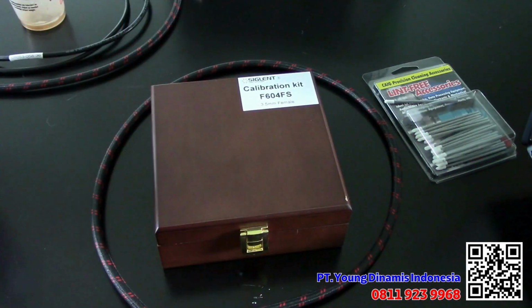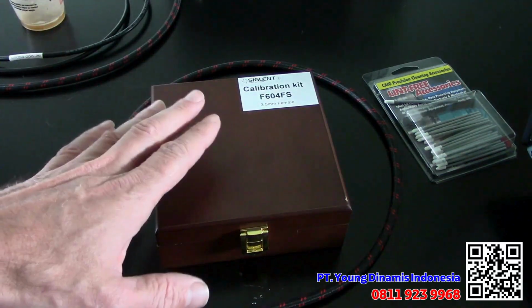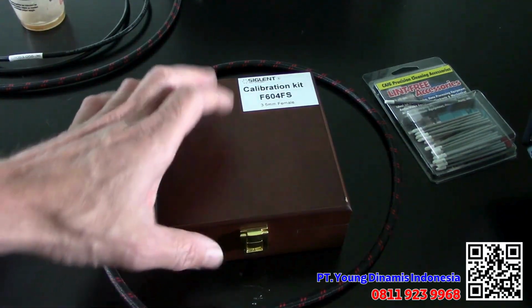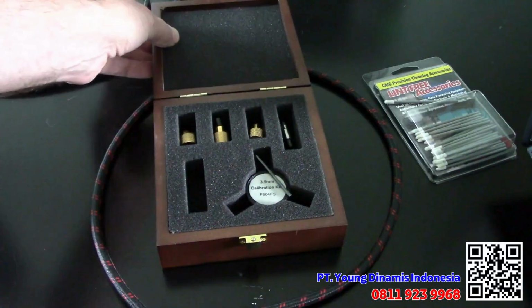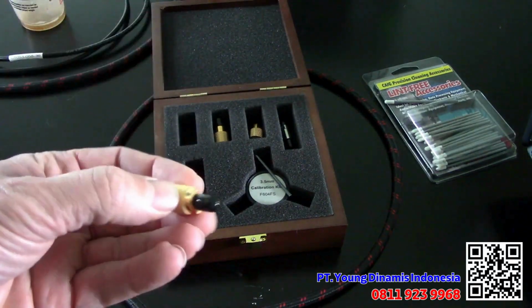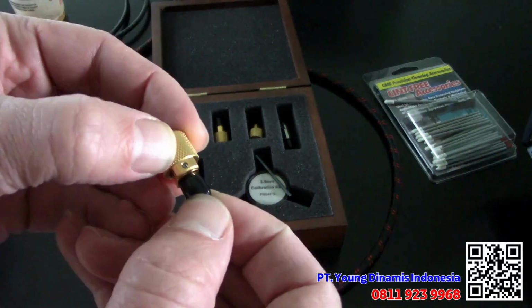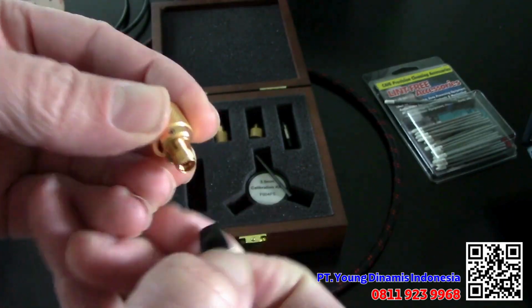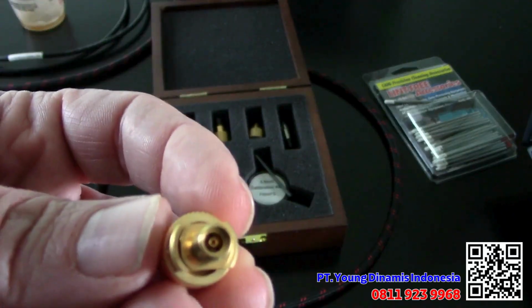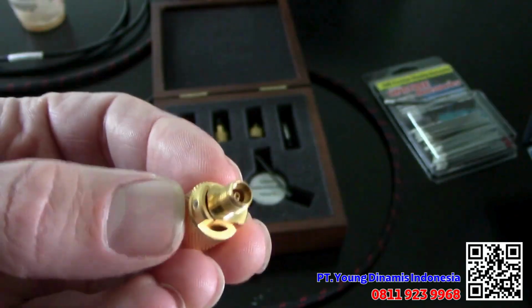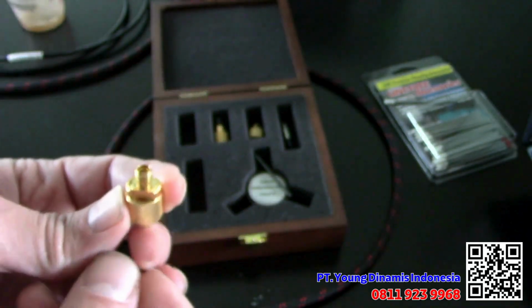Here we've got a Siglent F604FS female calibration kit. This is a 3.5 millimeter. Each of the short, open, and load elements has a cap. We want to remove that rubber element, and you can see with the 3.5 millimeter there is air as the dielectric between the center conductor and the outer. We've got some gold plating or metallized plating to help longevity.